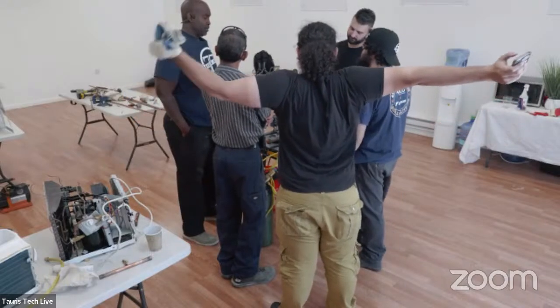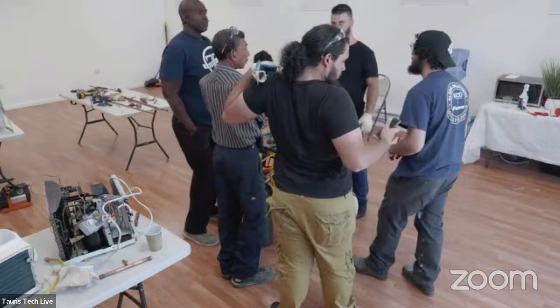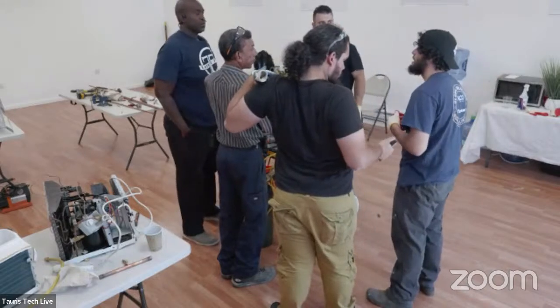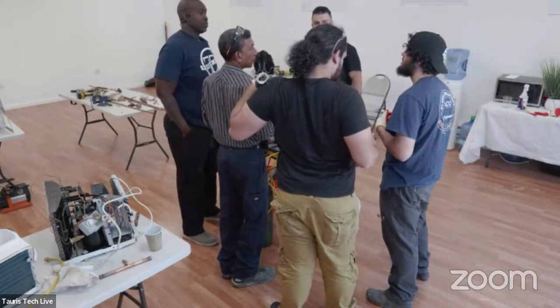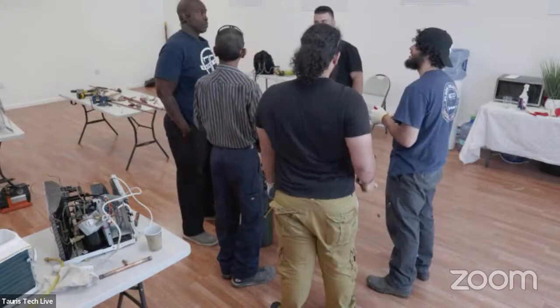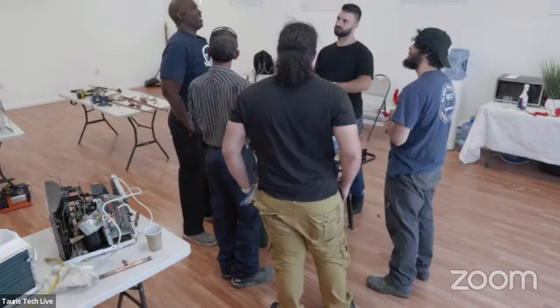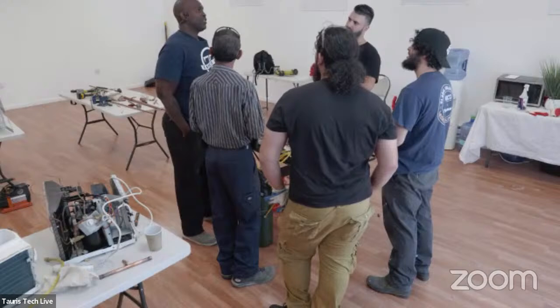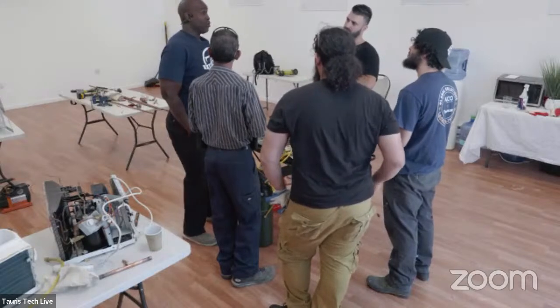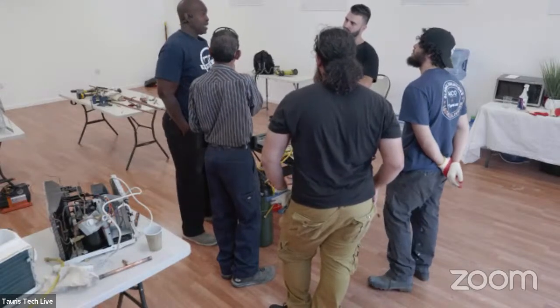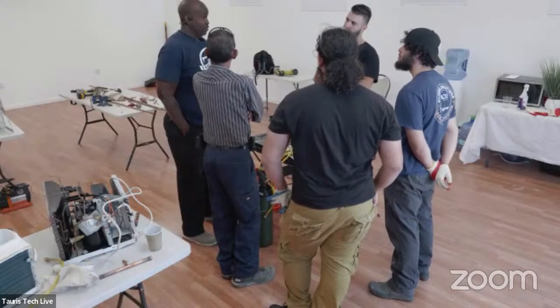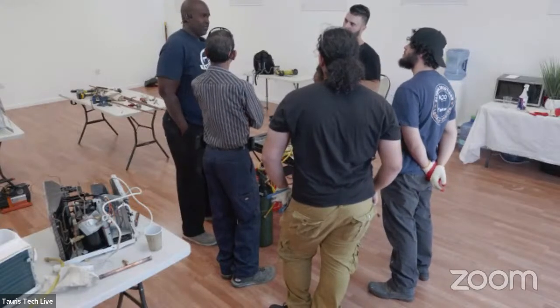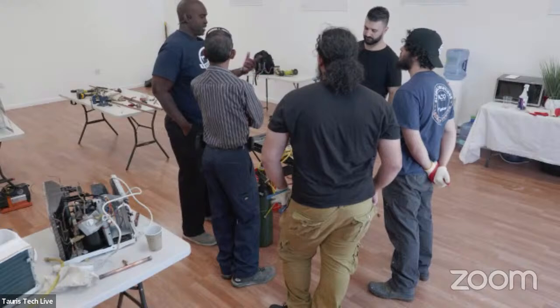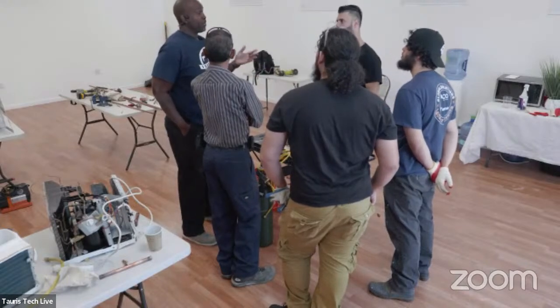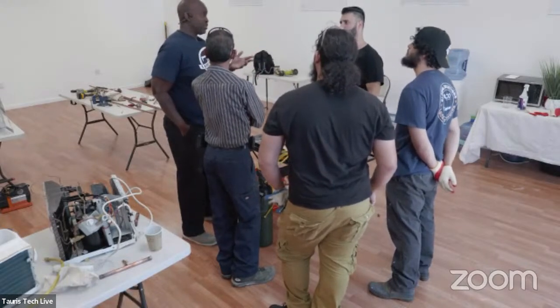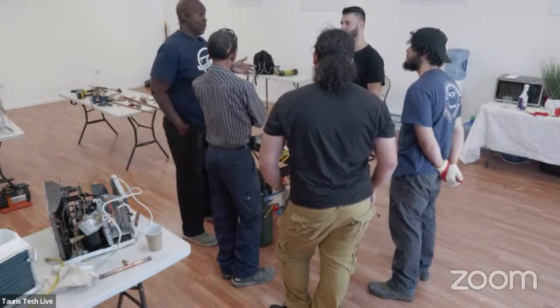So I heard someone say that when you vacuum it, if it holds a vacuum, you don't really need to leak test it, because it holds a vacuum. So that could be true, right? A vacuum test is a leak test. The problem is if it doesn't hold a vacuum, because a vacuum test is sucking in, it won't show you where the leak is. So you always have to do a pressure test to see where it's leaking, before you do the vacuum.